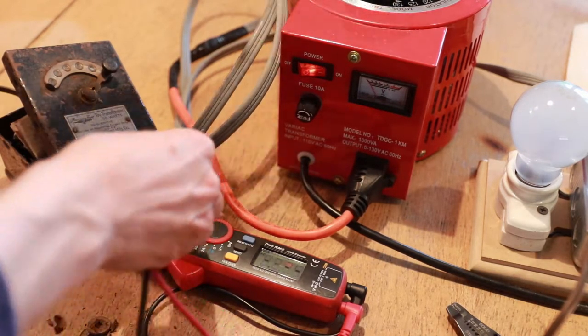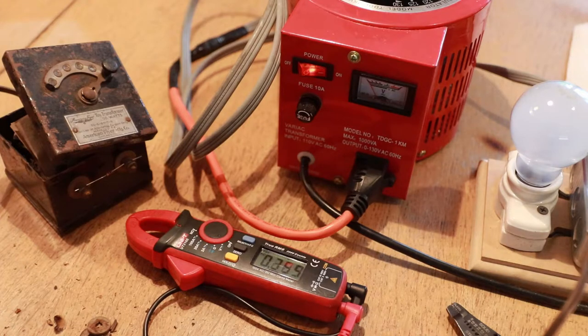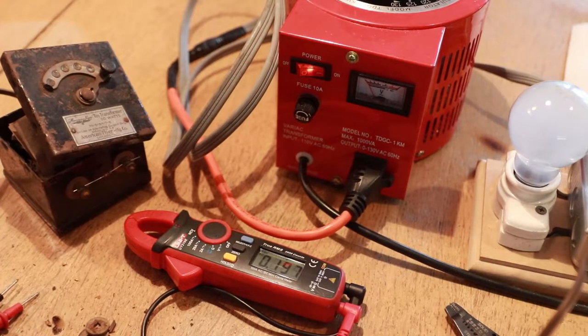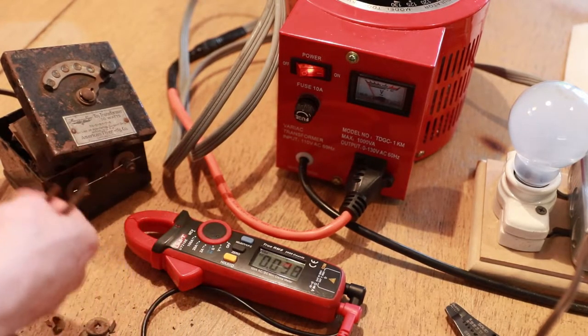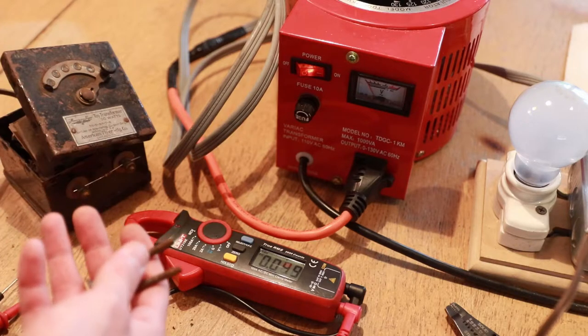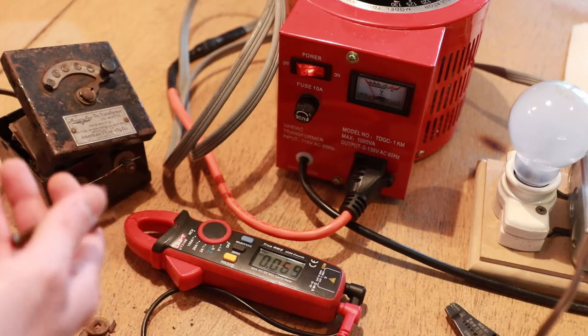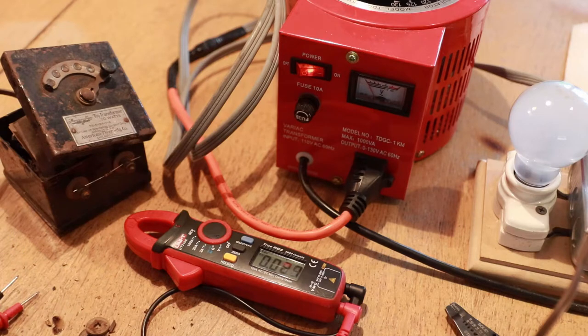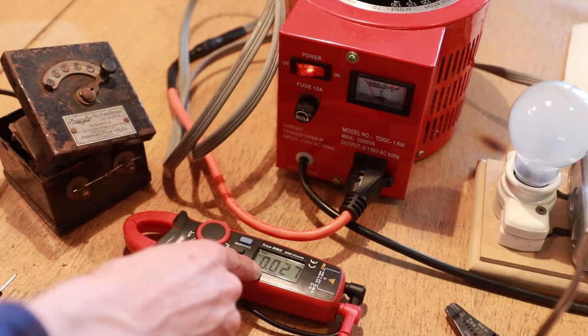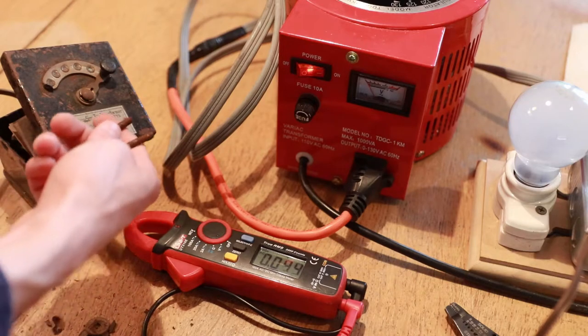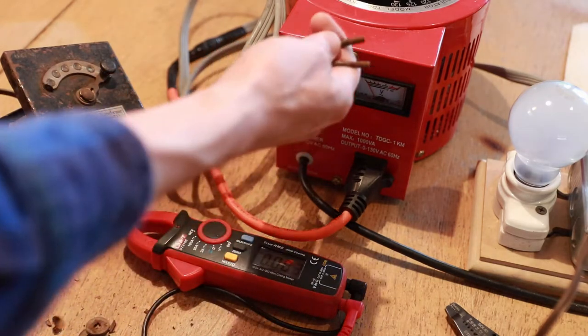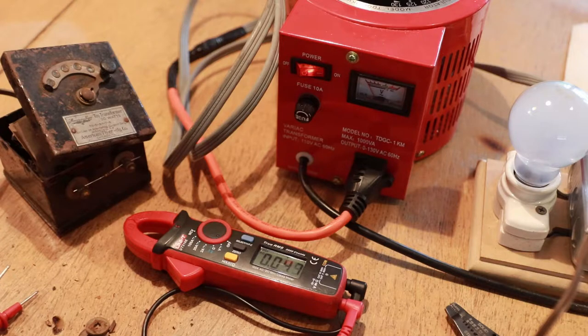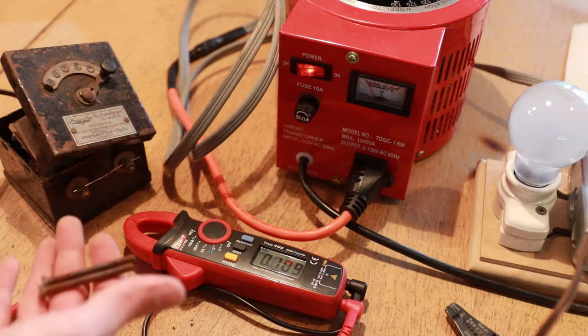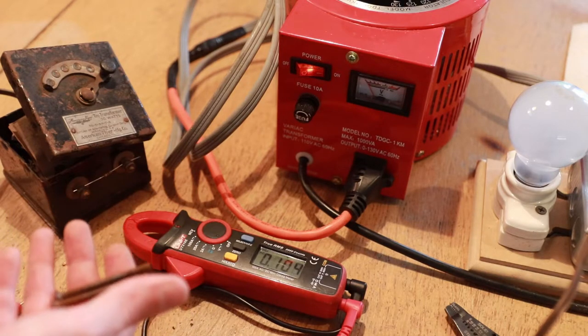So it is working, we're getting power. Now that grinding, buzzing sound sounds terrifying. However, keep in mind we've removed the bolts that constrain the laminations together on the transformer. Once we put these back in and crank them down, there's a good chance that vibration will go away. It's also a very good sign that we were able to generate all the voltage this is supposed to. Nominally it's 8 volts, but we've got a nice 120 volt AC input, and this is only rated for 110.